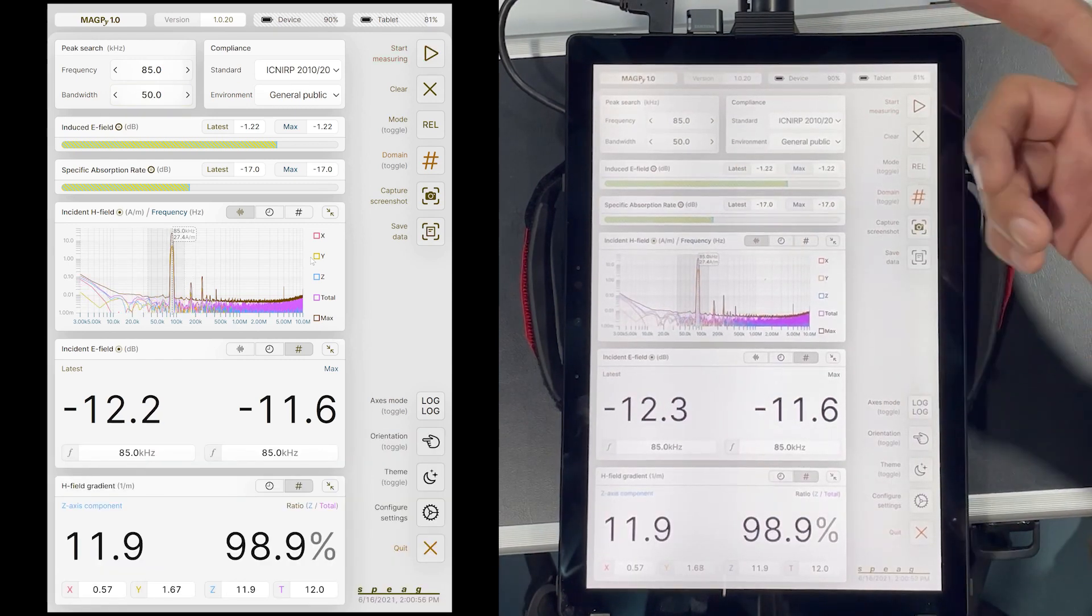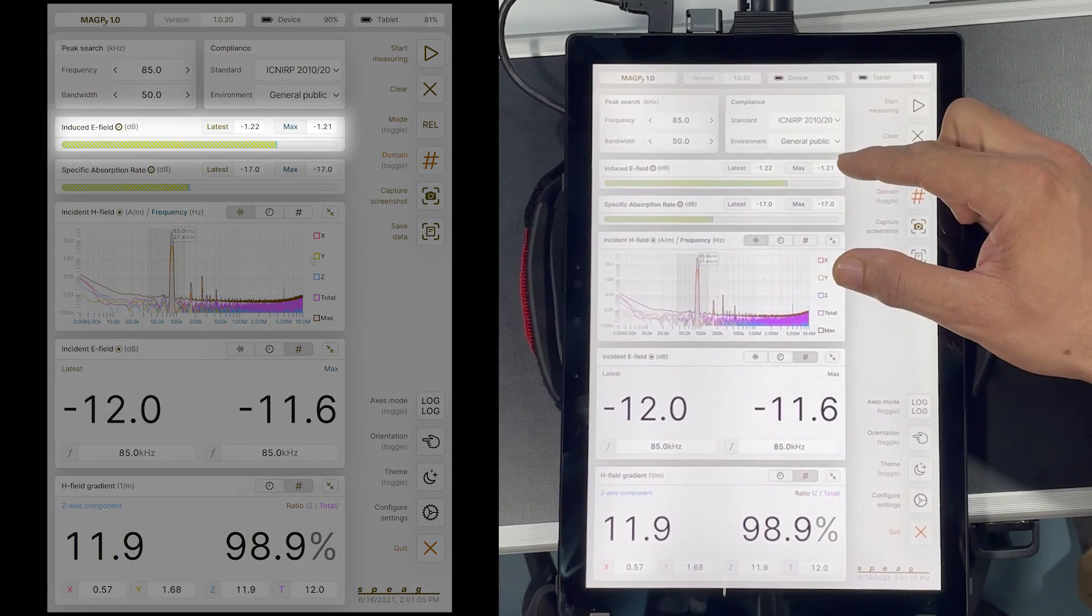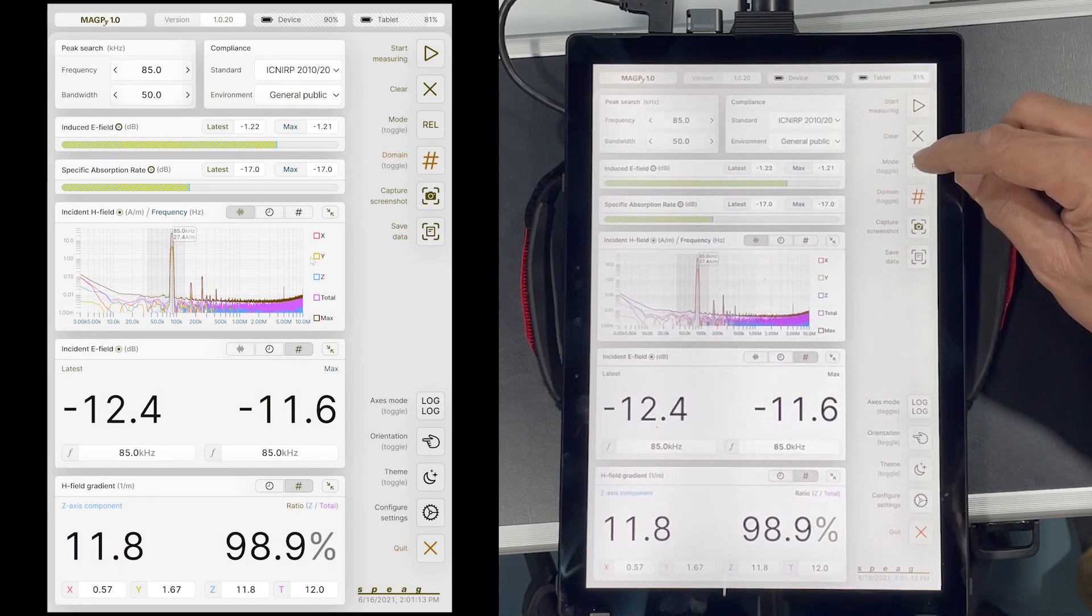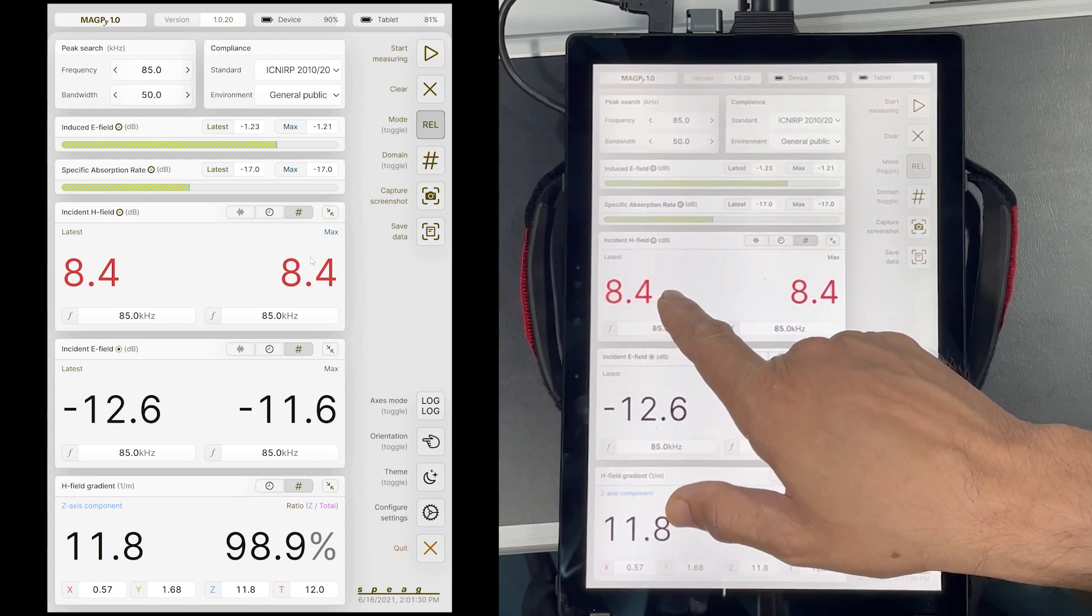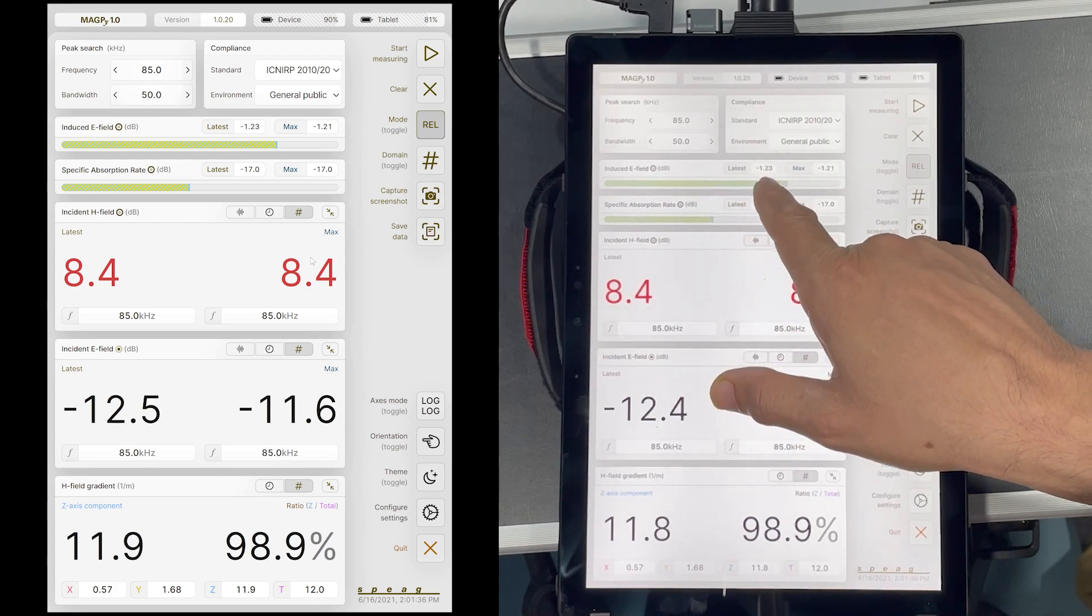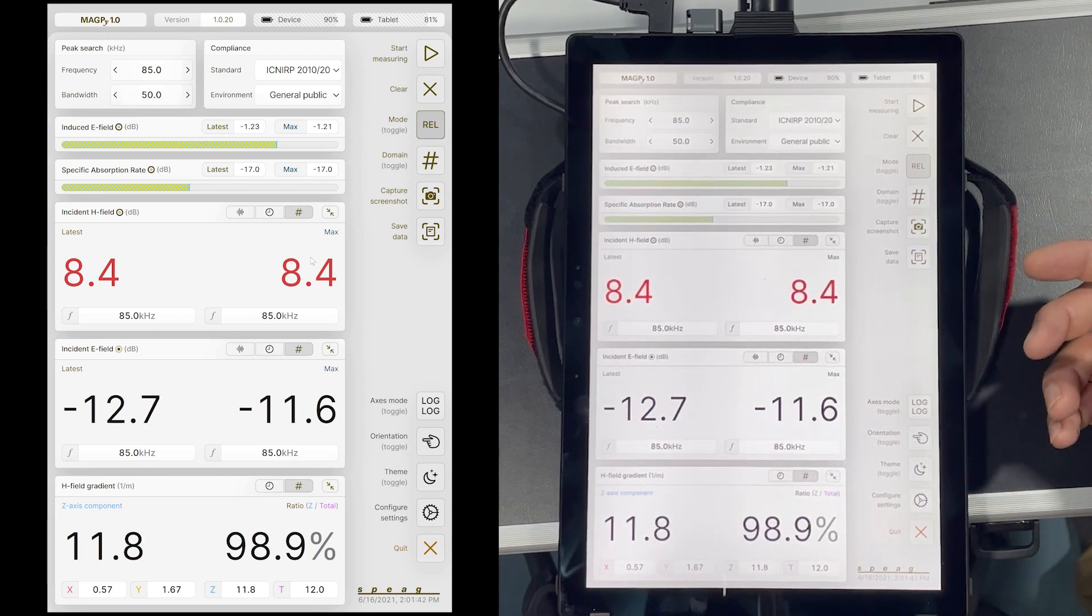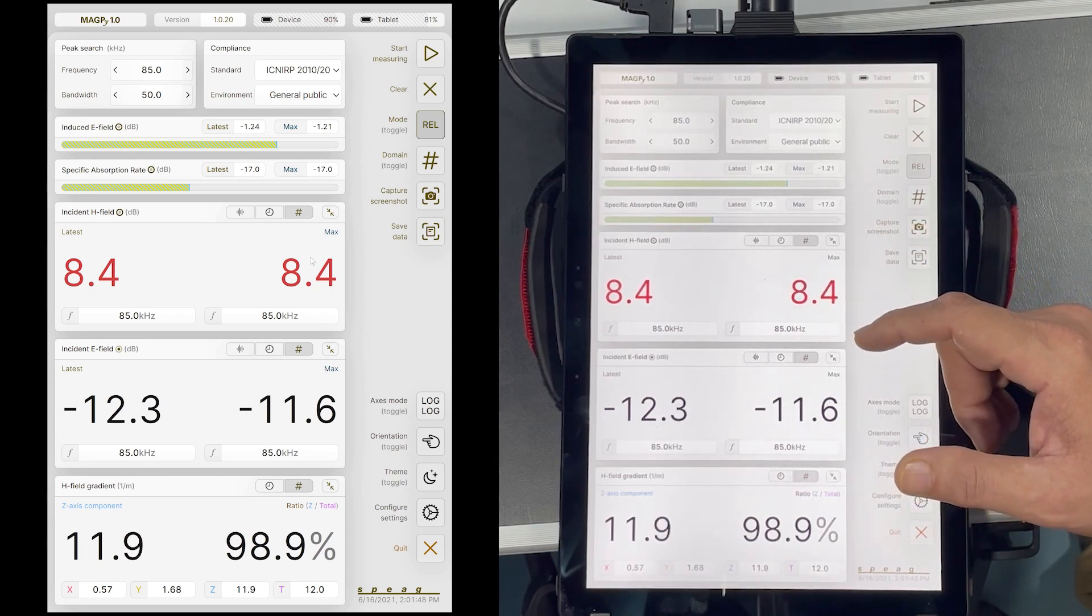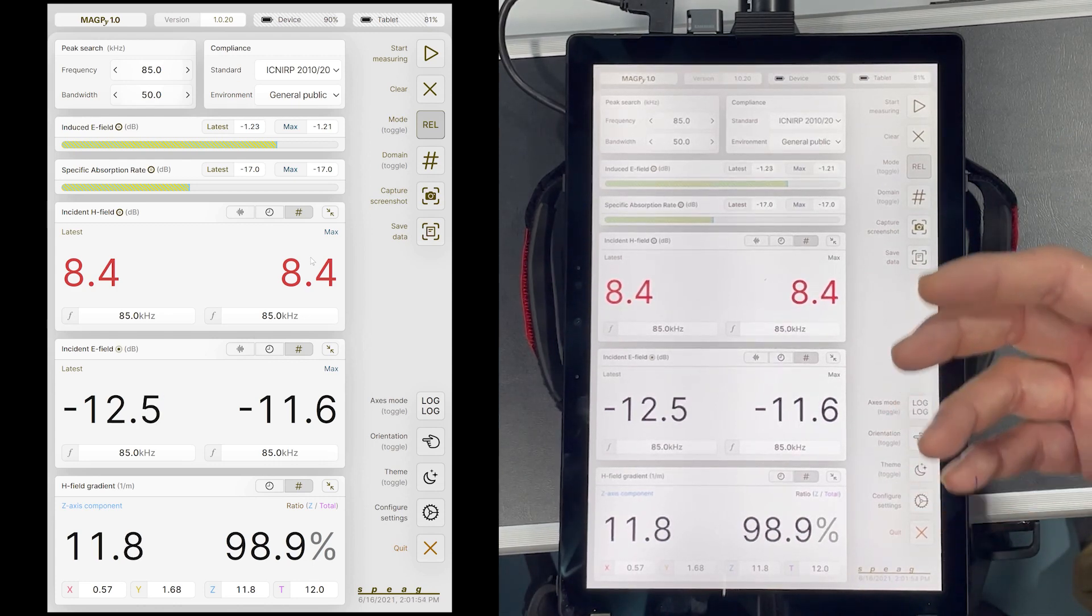Now, here is the exciting part of this device. In this bar here, the estimated induced E field is displayed and below is the estimated induced SAR. If I switch to relative mode, I see that the incident H field is 8.4 dB above the limit. But the conservatively estimated induced E field is 1.24 dB below the limit. This means that the device is compliant with the basic restrictions and therefore with the safety guidelines. Even though the reference levels are violated, very powerful Magpie can demonstrate compliance for sources which cannot be assessed by any other device.